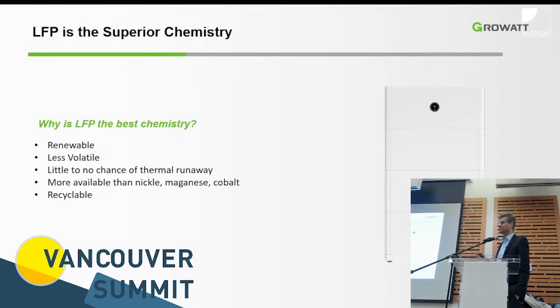The LFP chemistry, to my previous presentation, is the chemistry of choice for most manufacturers, because that's the one that you can get relatively easily through fire propagation testing and get it certified. The same applies to Growatt. They picked the LFP chemistry as well because it has little thermal runaway problematic and is maybe a little bit more cost effective, also because it has no cobalt in it. And from an environmental perspective, if you have customers that are concerned about mining operations, if it doesn't have cobalt in it, you eliminate that problem altogether.